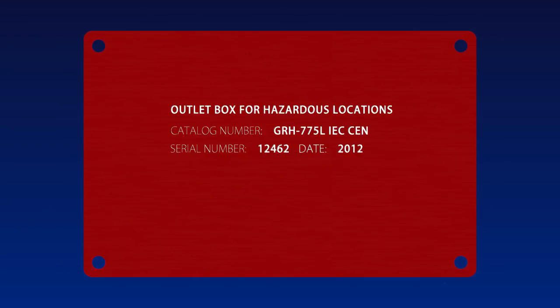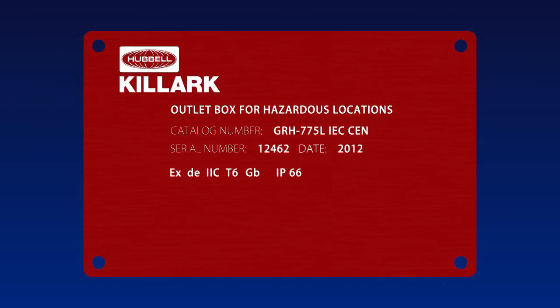Starting with the basic IEC marking, EX is used to show that the equipment is explosion protected. This is followed by the protection type, the equipment group, and then the gas or dust material group. Following that string is the temperature or T code. The actual temperature might also be included, if not redundant, with the other marking. Ingress Protection or the IP number could also be a required part of the nameplate. Of course, the manufacturer's name and location would also be included, as well as the Certificate of Compliance number.